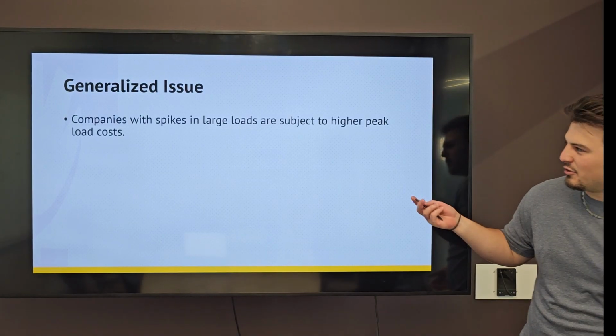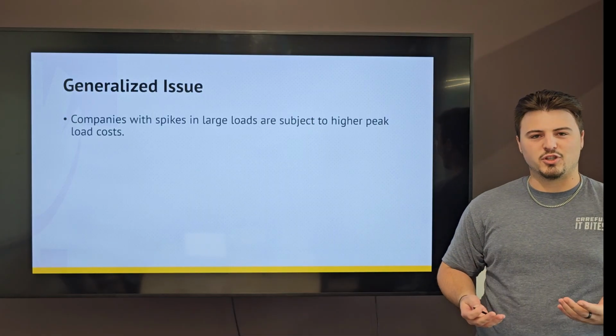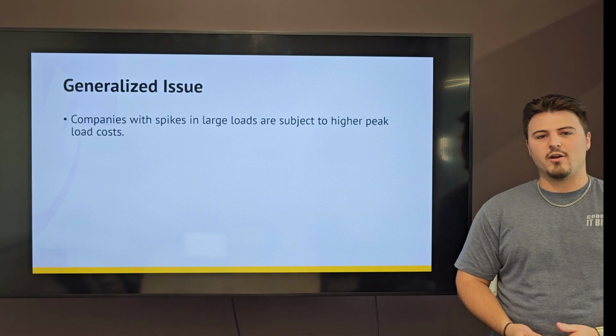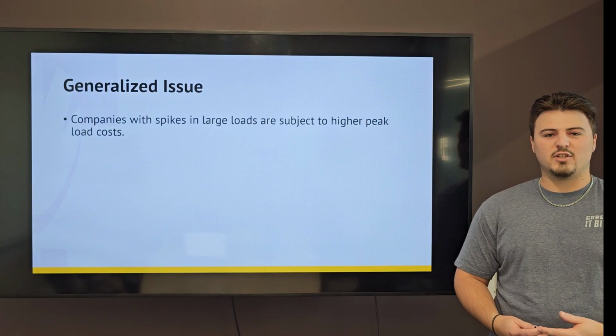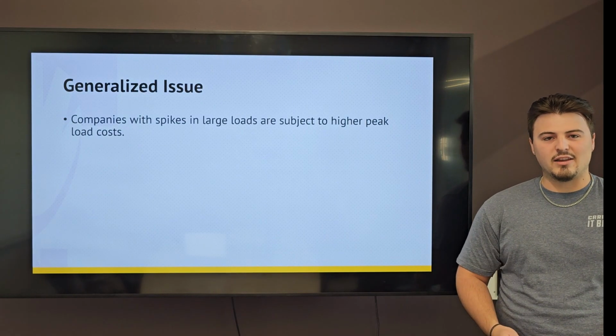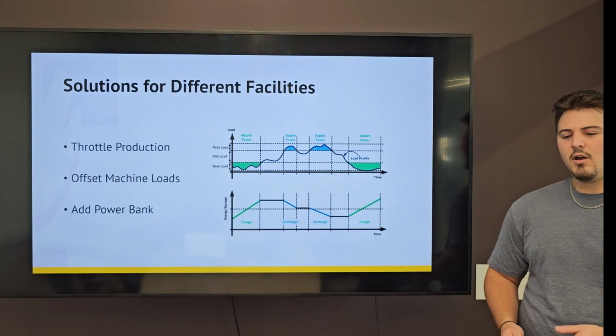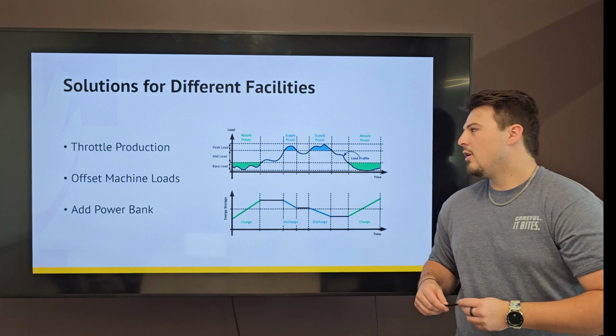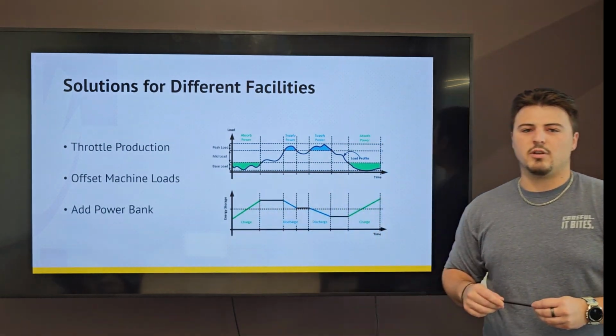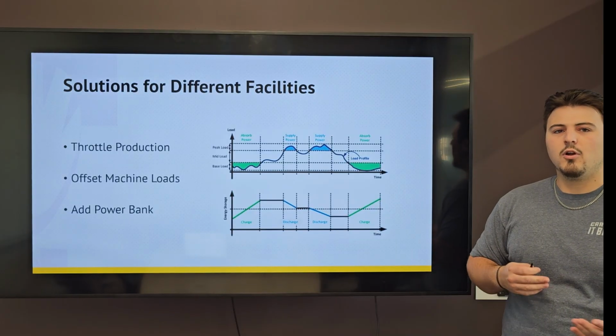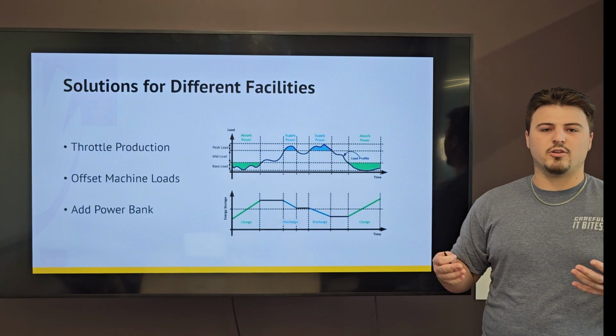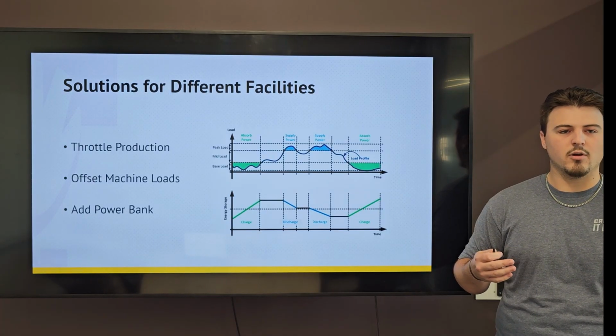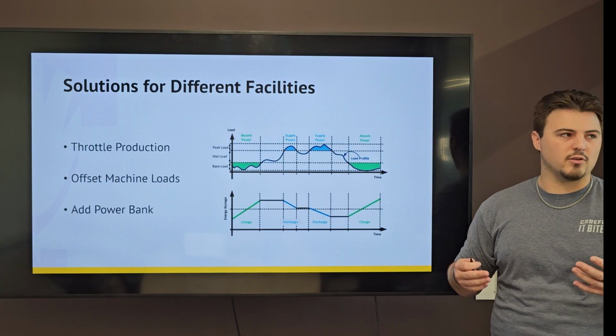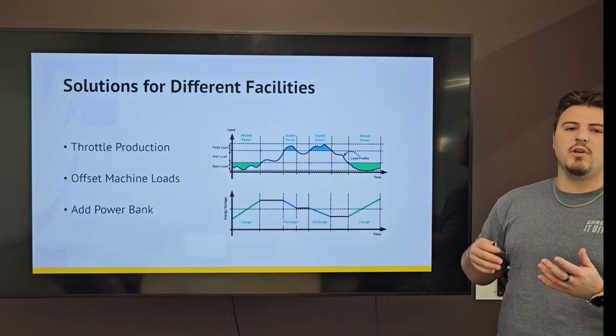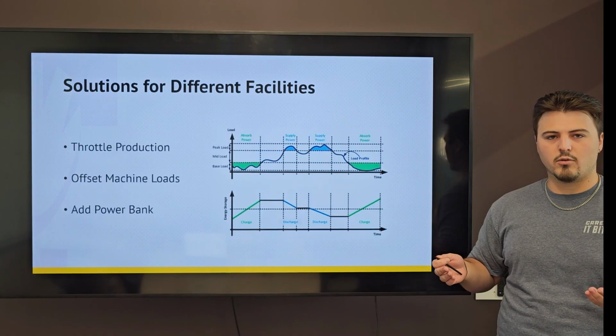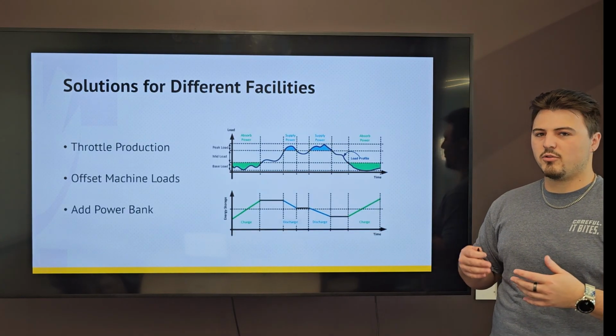First, begin with the generalized issue. Companies with varying machinery sizes all have varying power problems where they have spikes in their loads, which causes an increase in their costs overall. Some of the solutions to this, however, could be throttling production, where you actually go in and maybe with a variable speed control or a different method along those lines, you turn down the production value of the machine itself, maybe setting it to 70% instead of 100%, and being able to reduce your overall load at the time, and in turn being able to reduce cost.